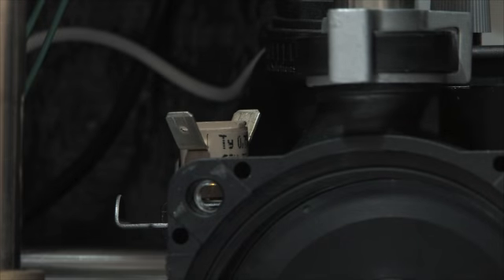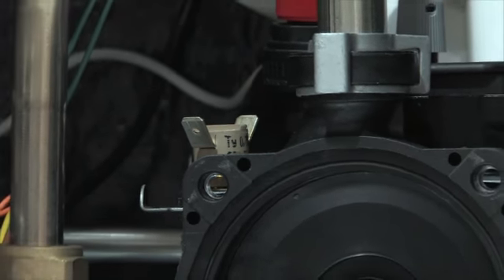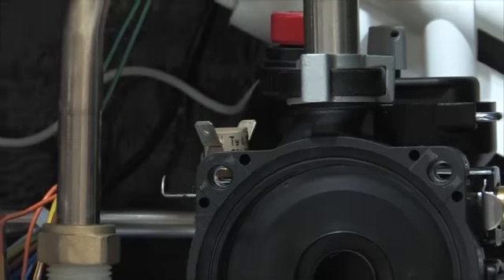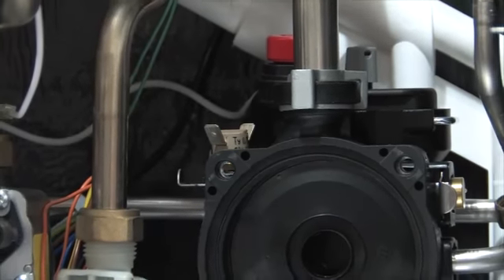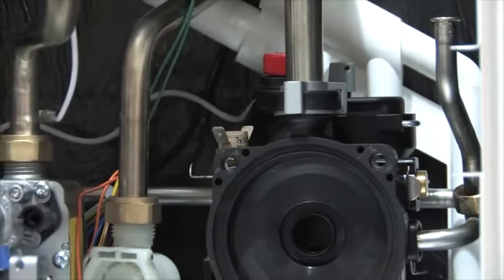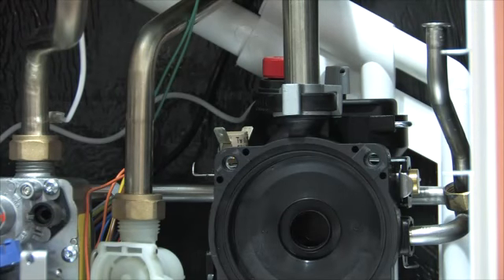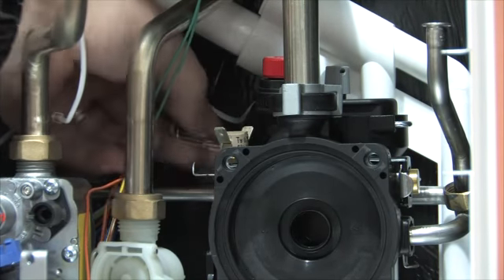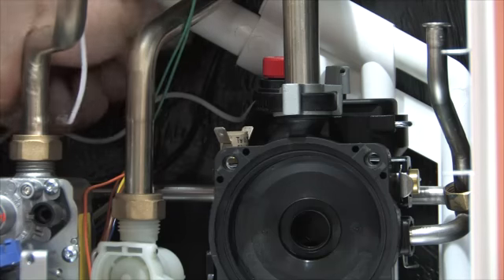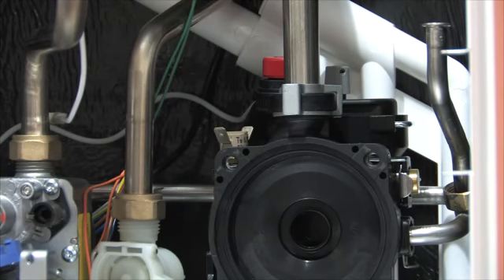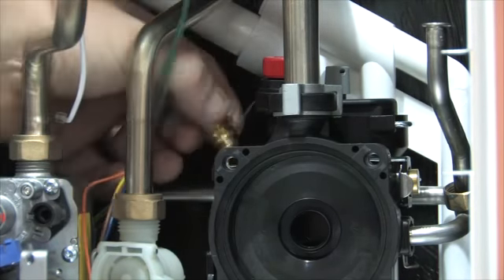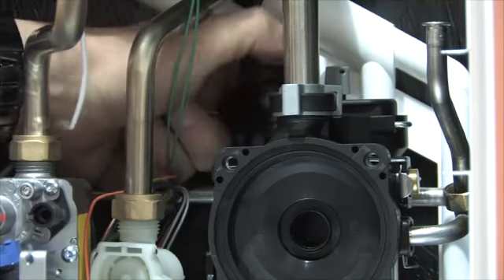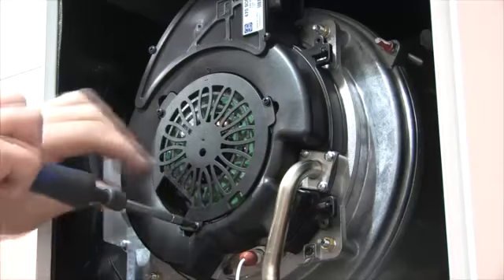The low water pressure switch, which automatically cuts the boiler off for low system pressure, pressure relief valve and automatic air vent, are all attached to the pump assembly. This is the only place in the boiler where O-rings are found. Elsewhere, compression fittings are used, which greatly reduces potential for leaks. Both the PRV and the auto air vent are retained by a single clip, which can be removed and each item removed individually. The fan PCB is available as a spare.